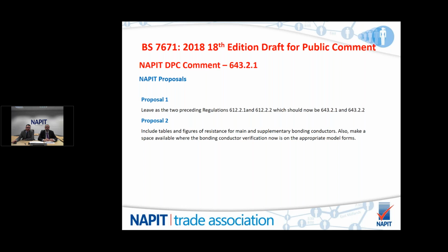So we have two proposals for Regulation 643.2.1. The first proposal is to leave the regulations as the two preceding regulations, which were 612.2.1 and 612.2.2, which should now be referred to as 643.2.1 and 643.2.2. And the second proposal is to include tables with figures of resistance for main and supplementary bonding conductors and make space available where the bonding conductor verification now is on the appropriate model forms. This enables you to record the measurement of resistance and compare it against a table of figures for that resistance, similar to what we do for the Zs values in the earth loop tables, where we make a measurement of earth loop values and it has to meet the maximum requirements of the various Zs tables.